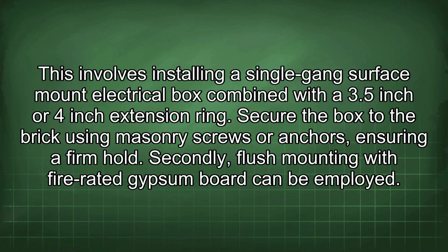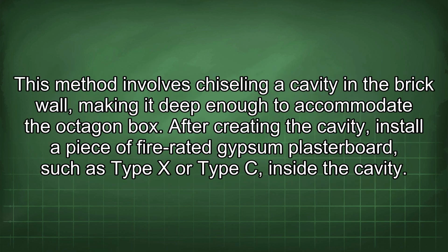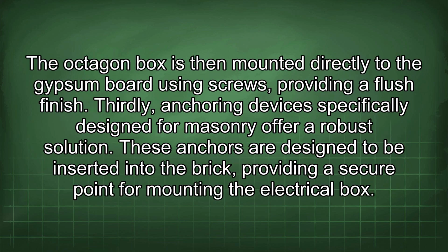Secondly, flush mounting with fire-rated gypsum board can be employed. This method involves chiseling a cavity in the brick wall, making it deep enough to accommodate the octagon box. After creating the cavity, install a piece of fire-rated gypsum plasterboard, such as Type X or Type C, inside the cavity. The octagon box is then mounted directly to the gypsum board using screws, providing a flush finish.